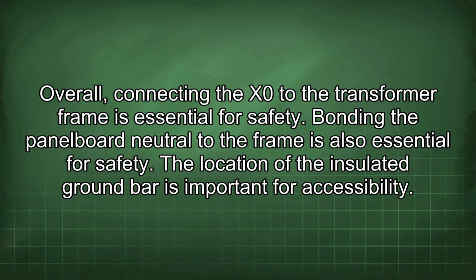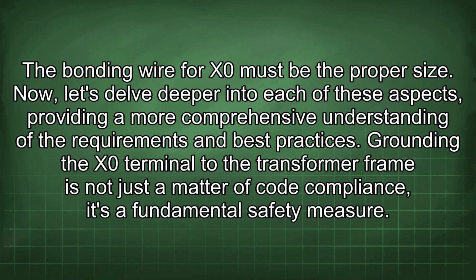Overall, connecting the X0 to the transformer frame is essential for safety. Bonding the panel board neutral to the frame is also essential for safety. The location of the insulated ground bar is important for accessibility. The bonding wire for X0 must be the proper size. Now let's delve deeper into each of these aspects, providing a more comprehensive understanding of the requirements and best practices.